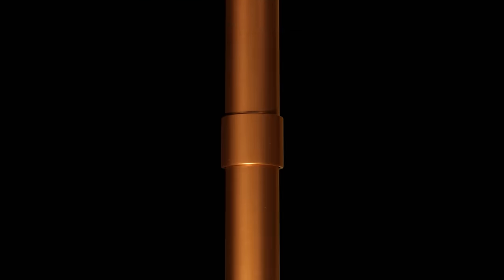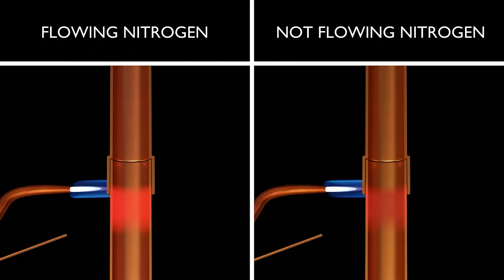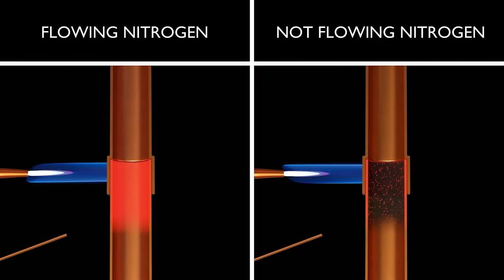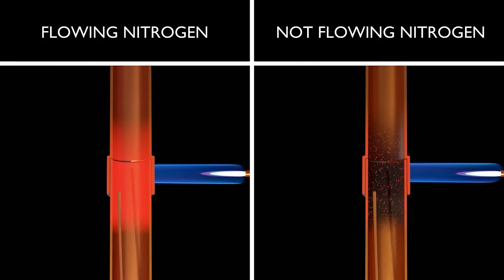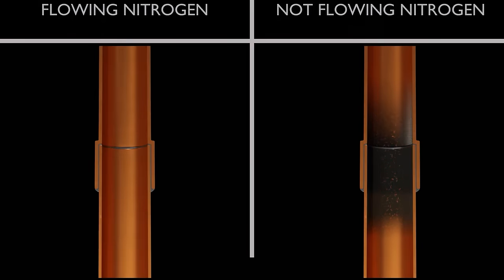Next, we're going to show why it's so critical to flow nitrogen at that 3 to 5 SCFH. If you fail to flow nitrogen, cupric or copper oxide can build up inside the tube, which can cause system contamination, clogged screens, dryers, and expansion valves.